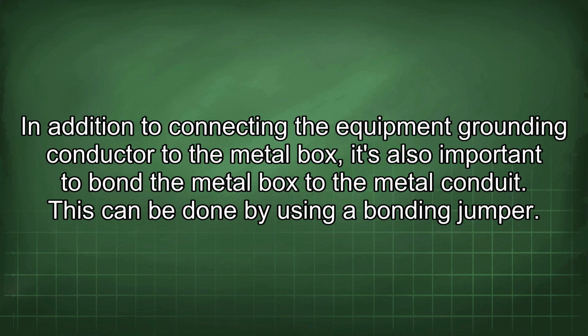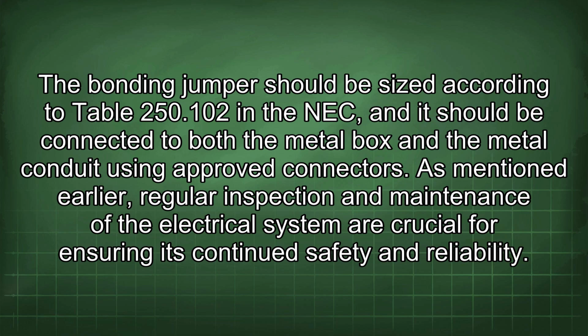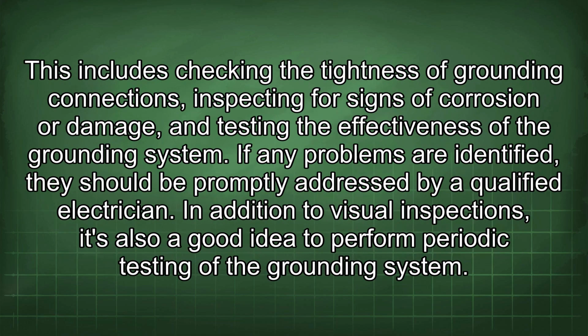In addition to connecting the equipment grounding conductor to the metal box, it's also important to bond the metal box to the metal conduit. This can be done by using a bonding jumper. The bonding jumper should be sized according to Table 250.102 in the NEC, and it should be connected to both the metal box and the metal conduit using approved connectors. As mentioned earlier, regular inspection and maintenance of the electrical system are crucial for ensuring its continued safety and reliability. This includes checking the tightness of grounding connections, inspecting for signs of corrosion or damage, and testing the effectiveness of the grounding system. If any problems are identified, they should be promptly addressed by a qualified electrician.